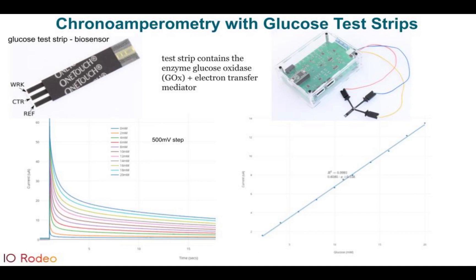If you connect the test strip to your potentiostat via the working, counter, and reference electrode connections, and put your sample on the end of it and step the voltage from, say, zero to 500 millivolts, you'll get a particular time course of current measured at the working electrode. That time course will depend on the glucose concentration in the sample. If you collect the currents at a particular time point and plot them as a function of glucose concentration, you see a tight correlation between glucose concentration and current. This is an amperometric test strip.